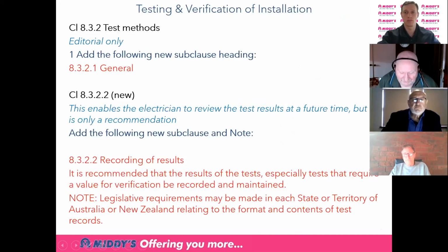Okay, we've had a lot of things thought about making it mandatory to record results when you go and do a job. You know, did I do an IR test on the mains? Did I do an IR test on my PN conductor, etc.? And what was the value? We thought about it a lot in the committee, and we could only come up with a recommendation. So the bit in red is where we've really been hitting home and has recommended the results of the tests, especially tests that require a value for verification, be recorded and maintained. Good idea. You probably take some photos with your camera these days of the job you finished, take a couple of sheets and take pictures of them too and file it all away. You never know when the regulator's going to come knocking and say, what results did you get? Once again, recommended only. Thank you.